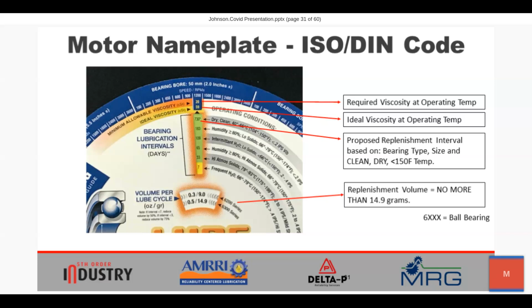Further, based upon operating conditions where we have dry, clean, low to moderate temperature, low vibration, we see the calculated replenishment interval. This value is based on a DIN standard that was provided to us by design engineers working in conjunction with SKF and FAG bearings back in the 80s.